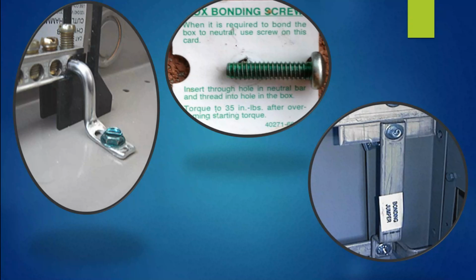So here are just some examples of the other type. Again, here on the right we do see another bus bar that was made that makes that connection, or a strap. Here we see a really common strap that we see in a lot of residential-type panelboards or panel enclosures, this one right here. Because this allows you to remove it if it's going to be used downstream as a remote distribution panel or whatnot, or different applications. So here you install it.